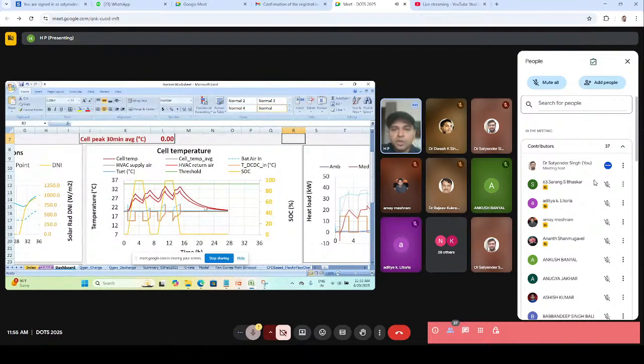So the criteria to design the cooling system here is that the manufacturer of the cell provides a certain threshold, shown here as this green line. You always have to maintain the peak temperature below that threshold, and if you do, the manufacturer can guarantee the performance of the cell.